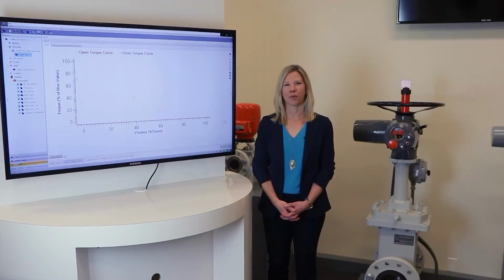Now we are moving to one of the most important fundamental diagnostic features: torque profiling. DCMlink is able to run and archive torque curves, perform and schedule partial stroke tests, and compare the actuator's current performance versus its historical records. Based on resulting data, users can determine the optimal time to schedule a valve maintenance.